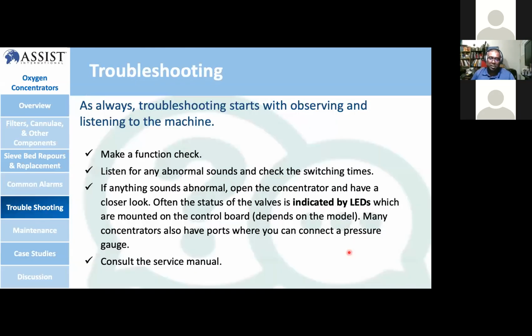So when you do troubleshooting, always have an observation of listening to the machine sound. Make sure the functional check is important. Listen for any abnormal sound, like check the switching time, the valve switching time, all that. Any abnormal noise in the oxygen concentrator, you need to check and take a closer look.